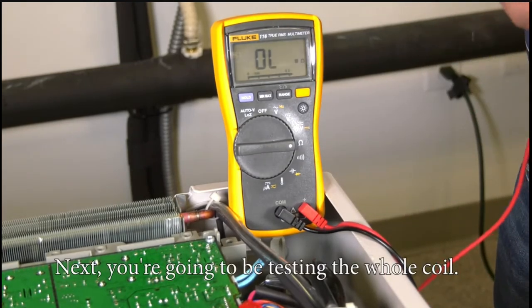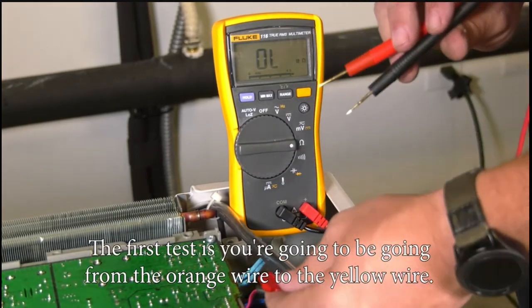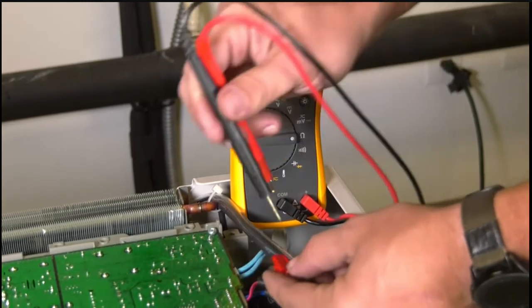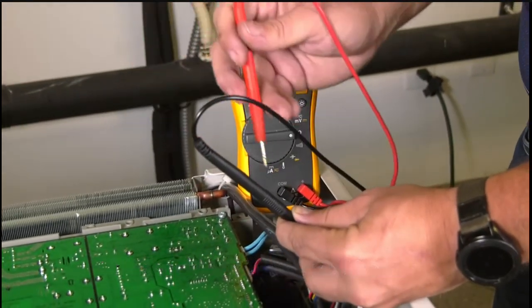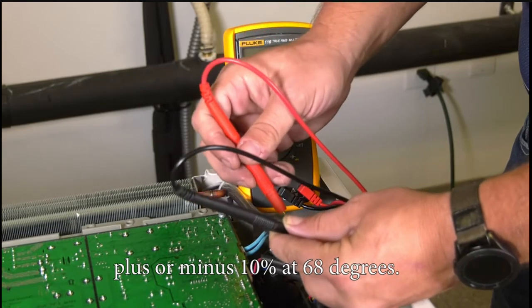Next you're going to be testing the whole coil. The first test, you're going to be getting a reading of 92 ohms plus or minus 10 percent at 68 degrees.